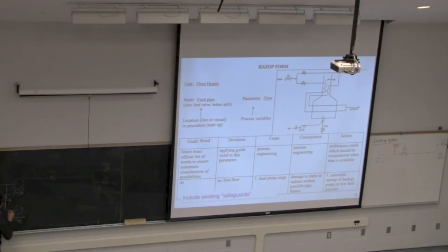Okay, so there's this valve here, and we'll put an asterisk here because I don't have a good symbol for that, and I don't want to clutter this diagram with too many lines just yet. So that asterisk is a note that this valve needs to have some alarm on it or some monitoring to make sure it's always open, because this is a critical instrument. This pump here we want to have available.